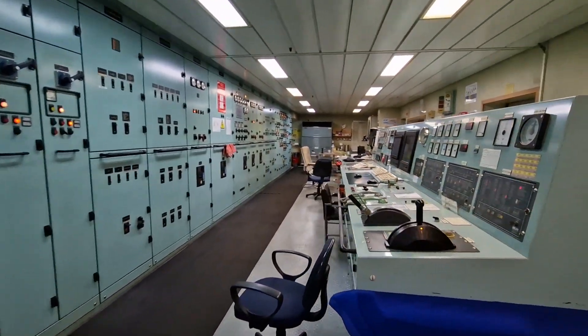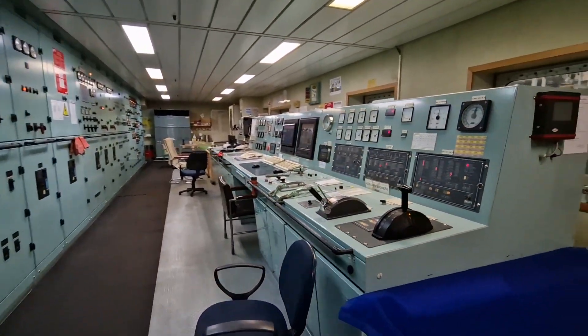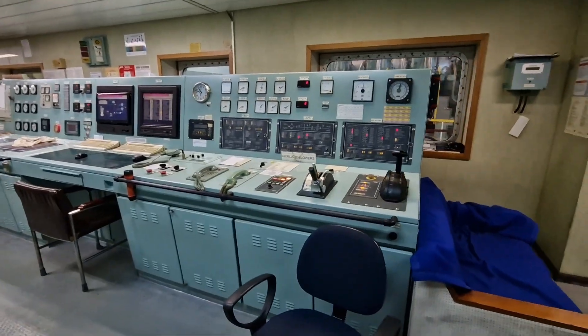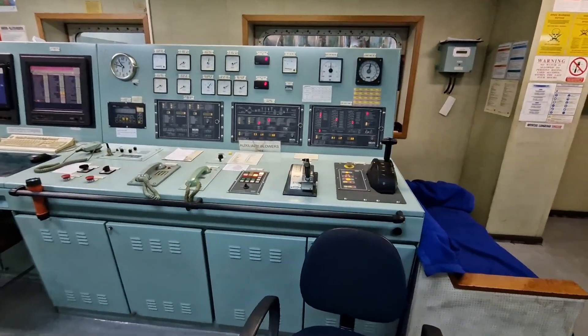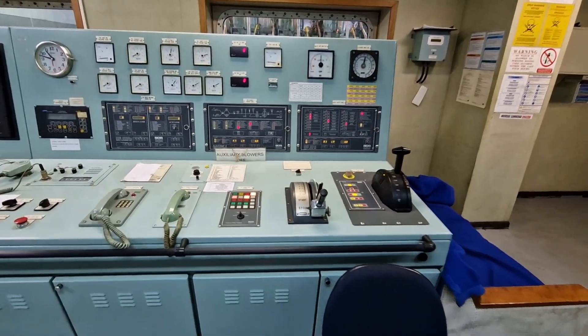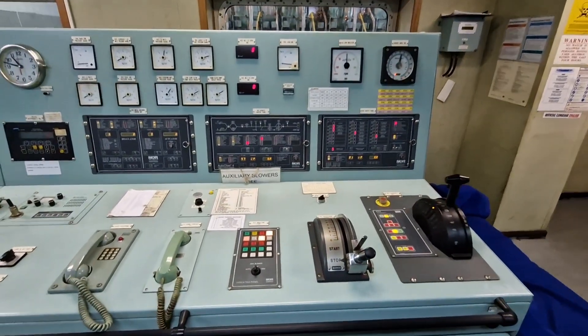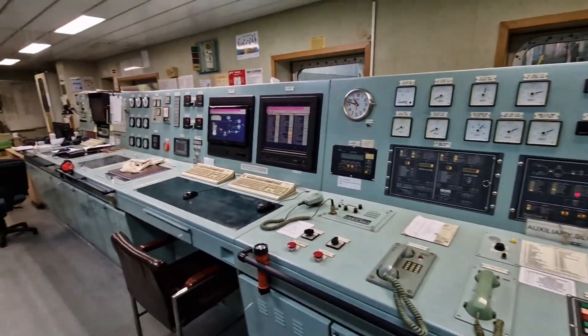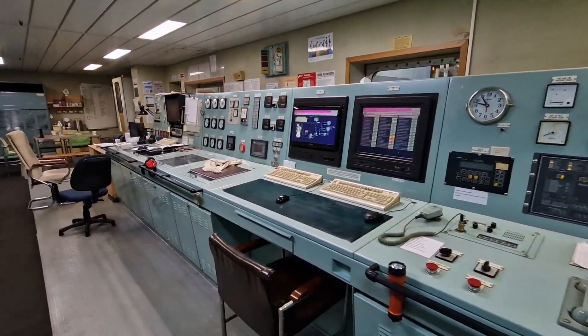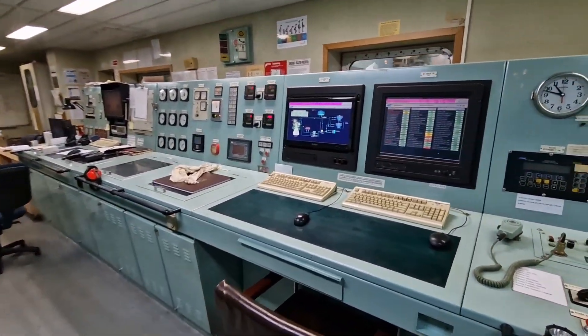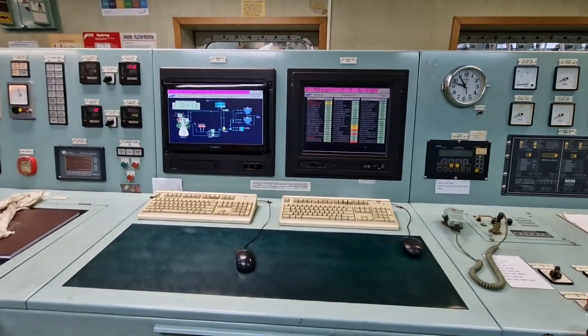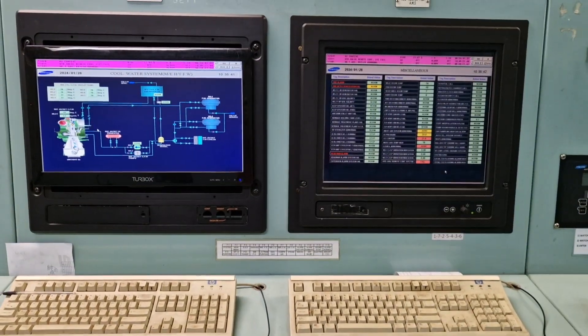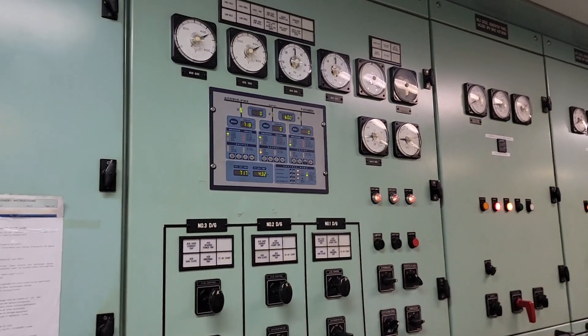These are the conditions I received from the engineers to start diagnosing and eliminating the malfunction. The first thing I asked was to carry out a test in order to observe how the synchronization takes place. And of course, everything went well and the generators properly shared the load.